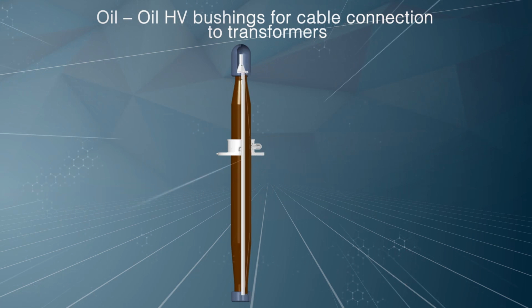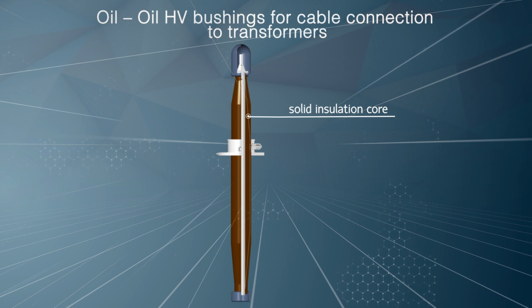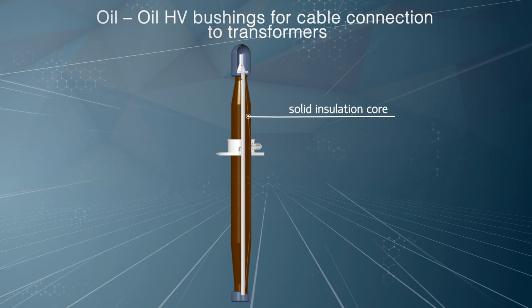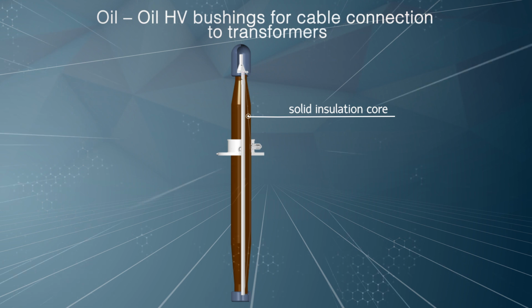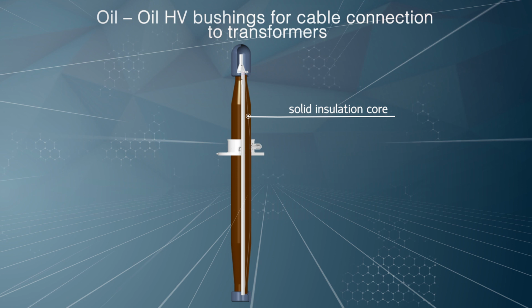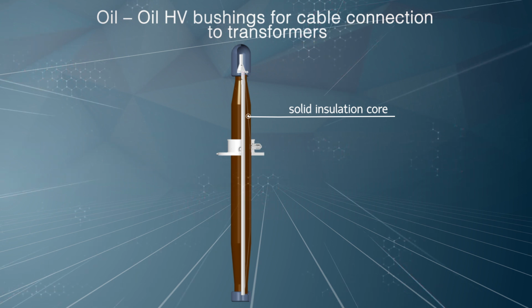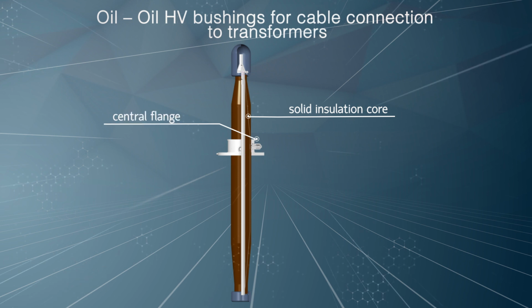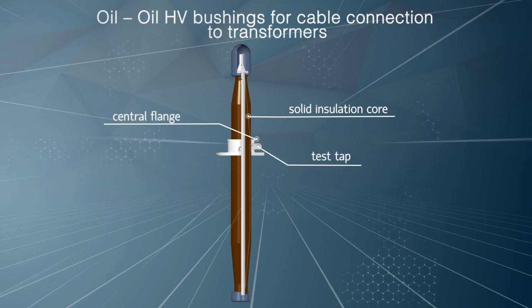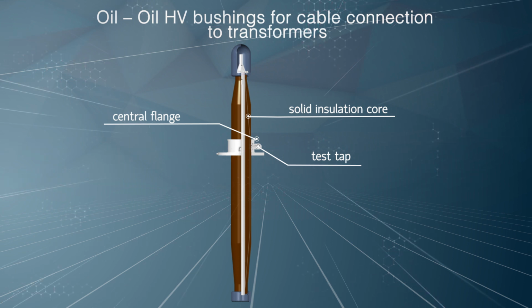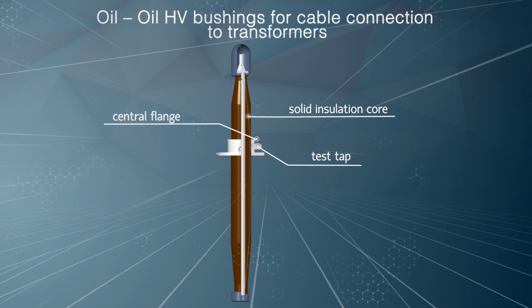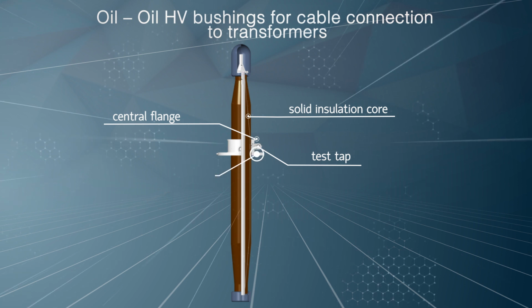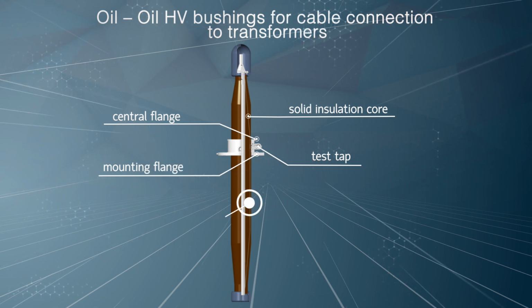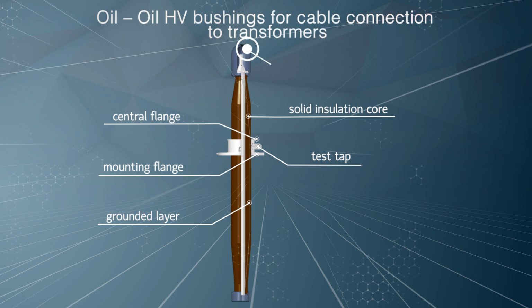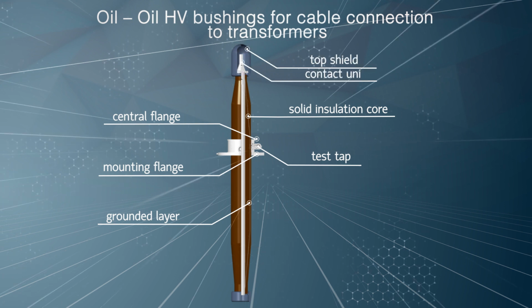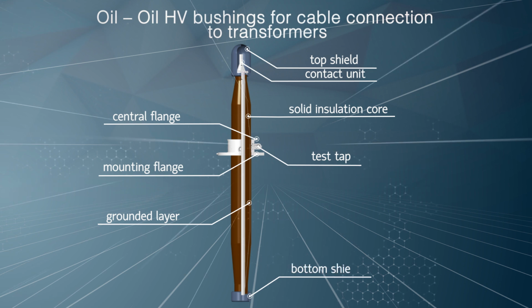part of the bushing. The bushing consists of the following elements: a solid insulation core, made by winding of insulating paper on a central tube with subsequent saturation in epoxy compound, RIP insulation. They use conductive liners, separating paper layers to equalize the electric field. A central flange with a test tap on it. In operating conditions, the test tap is connected with an extended test tap, positioned on the plate of the cable gland cover outside. The extended test tap must be effectively grounded during operation. A mounting flange with an eye bolt for lifting the bushing and a stopper for air outlet from the transformer tank. A top unit. A bottom shield.